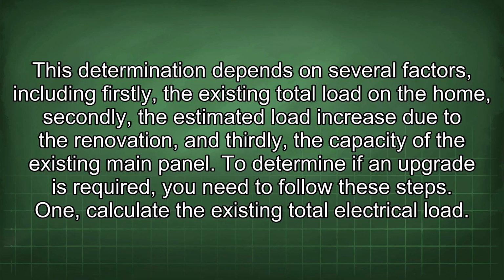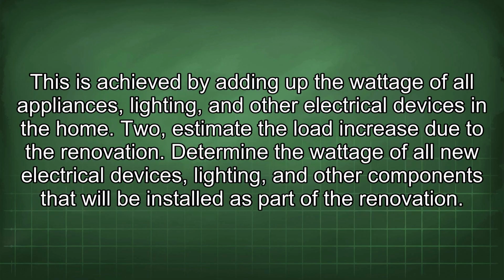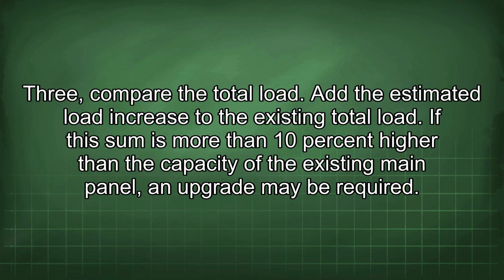1. Calculate the existing total electrical load. This is achieved by adding up the wattage of all appliances, lighting, and other electrical devices in the home. 2. Estimate the load increase due to the renovation. Determine the wattage of all new electrical devices, lighting, and other components that will be installed as part of the renovation. 3. Compare the total load. Add the estimated load increase to the existing total load. If the sum is more than 10% higher than the capacity of the existing main panel, an upgrade may be required.